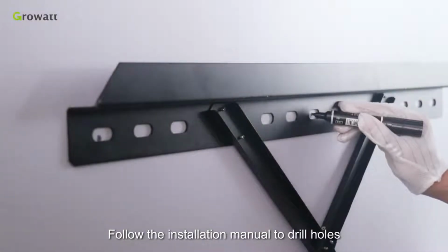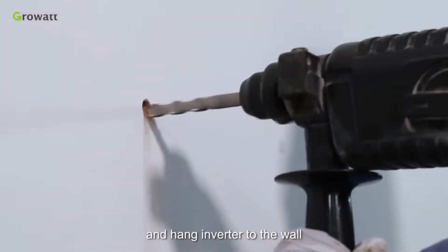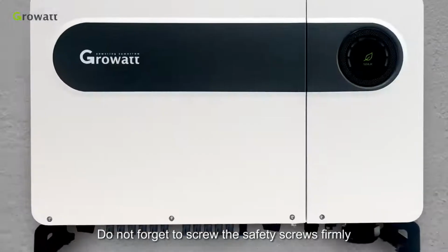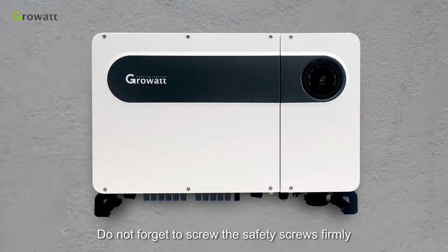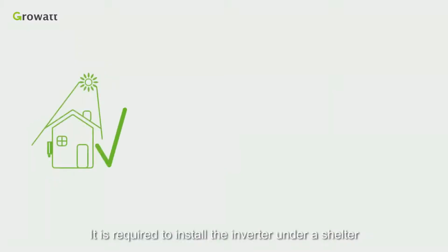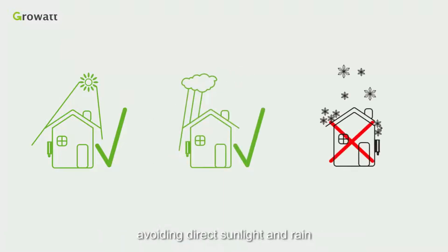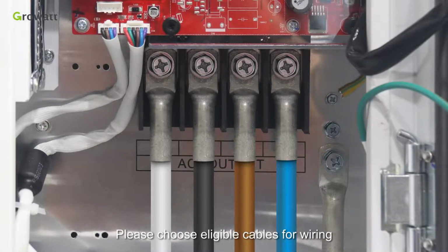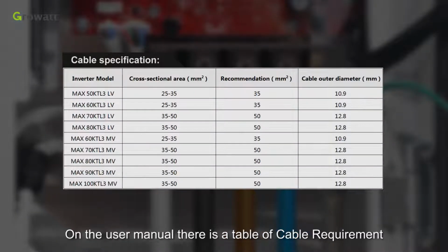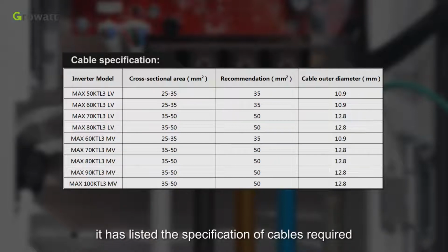Follow the installation manual to drill holes and hang the inverter to the wall. Do not forget to screw the safety screws firmly. It is required to install the inverter under a shelter, avoiding direct sunlight and rain. Please choose eligible cables for wiring. On the user manual, there is a table of cable requirements. It has listed the specification of cables required.